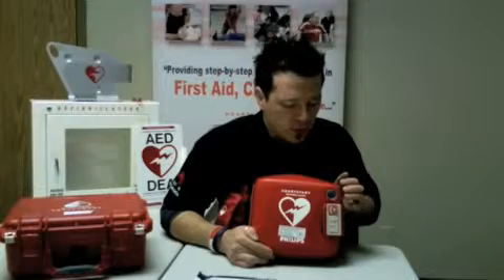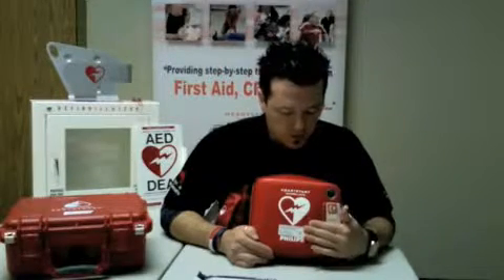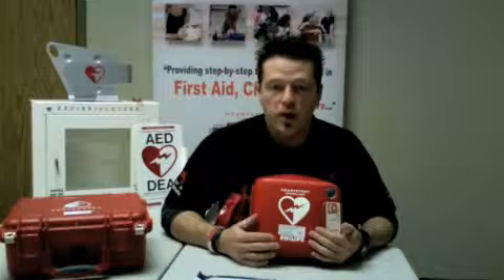In other words, if this little green light is flickering, that means that the defibrillator itself has checked itself every day, every week, every month, to make sure that it's in working order. Also, if you notice that the defibrillator has no flickering green light, or for some reason has started chirping, it is mandatory to do the servicing.